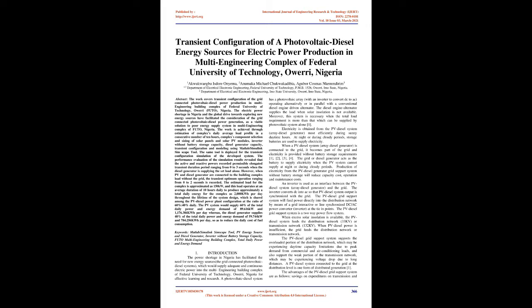Production of electricity from the PV diesel generator grid support system without battery storage will reduce capacity cost, operation, and maintenance costs. An inverter is used as an interface between the PV diesel system, array diesel generator, and the grid. The inverter converts DC into AC so that PV diesel system output is synchronized with the grid. The PV diesel grid support system will feed power directly into the distribution network by means of a grid interactive or line synchronized DC/AC power converter, inverter, at the tie-in points.